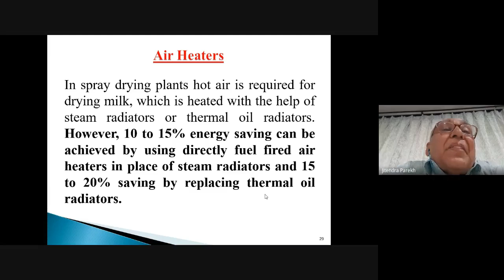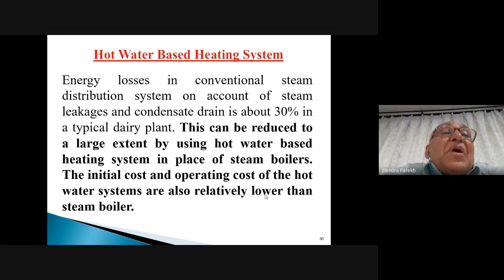Now, a hot water based system is also recommended, because we find that in a conventional steam distribution system, on account of steam leakage and condensate drain, the loss is about 30% in a typical dairy plant. This can be reduced to a large extent by using a hot water based heating system in place of the steam boilers. The initial cost and the operating cost of hot water systems are also relatively lower compared to the steam boilers. Next, please.